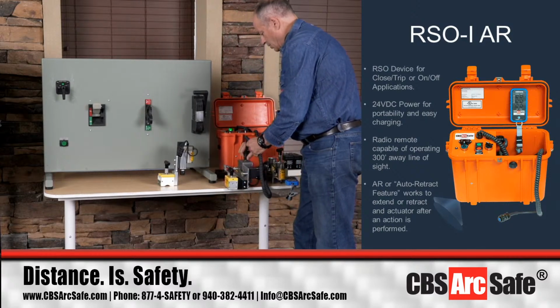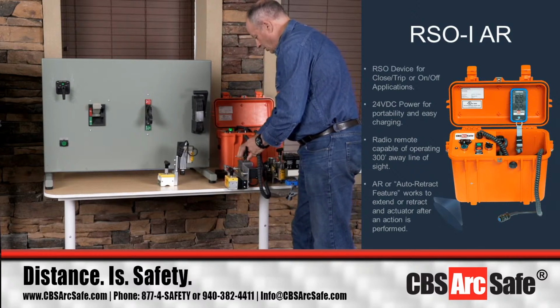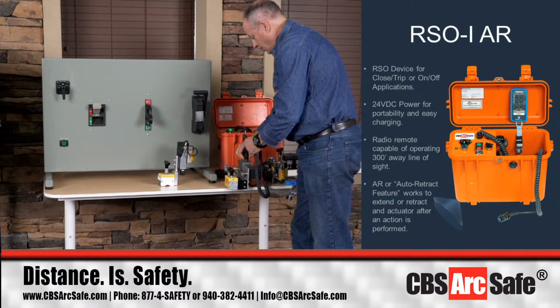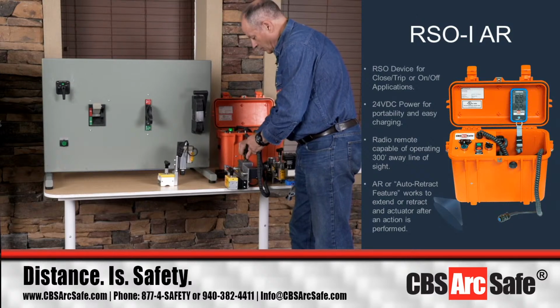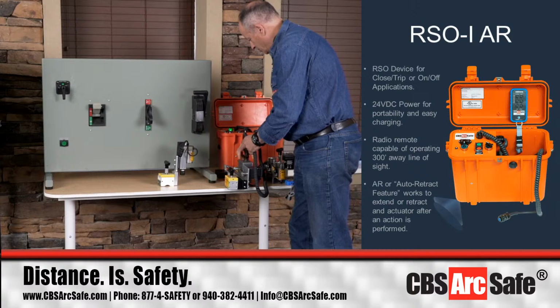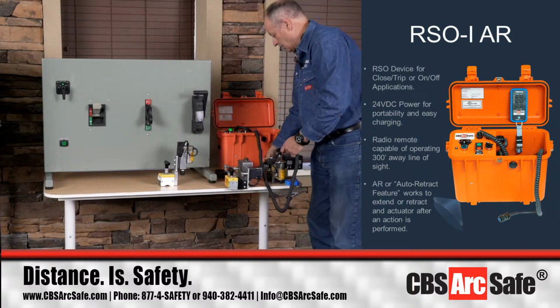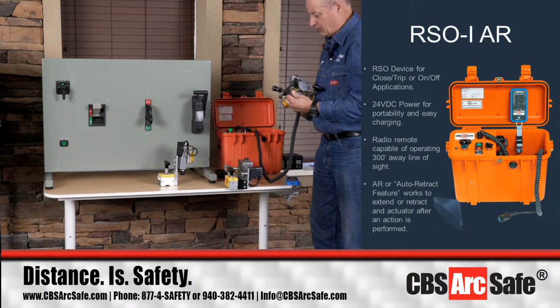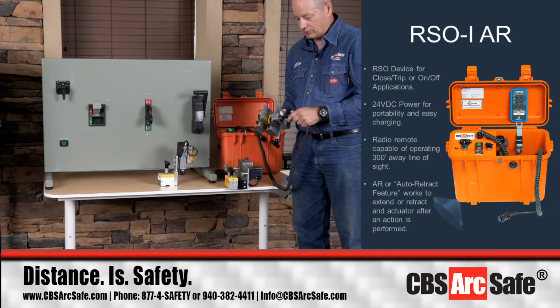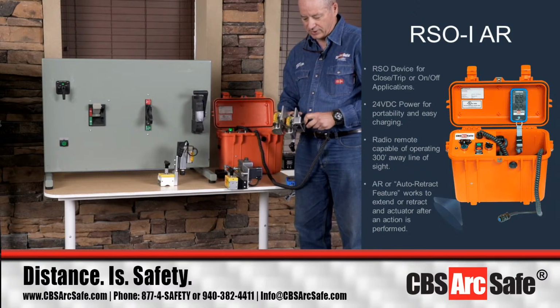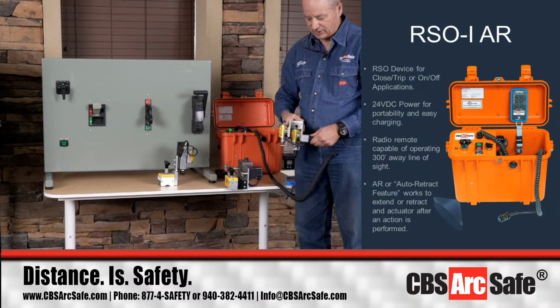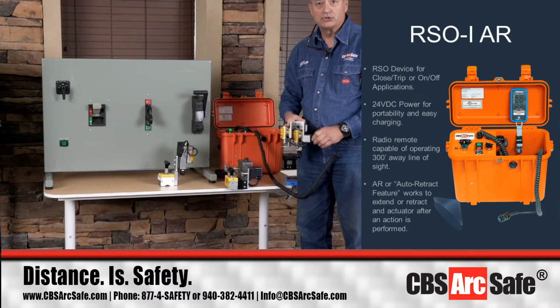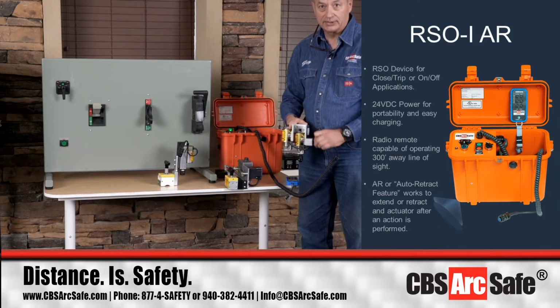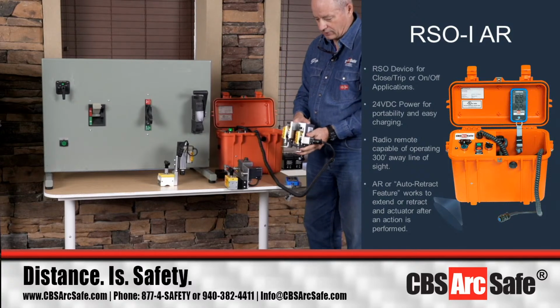We can use the RSO-I to trip and close a Westinghouse DS breaker. Now, one of the things you're going to see is that if I have AR on, and we always encourage people to check the device before they put it on the breaker. Right now I have AR off, and the reason I'm holding it like this is I want you to watch the solenoids and what happens if I move the AR on. Okay, so here it is.